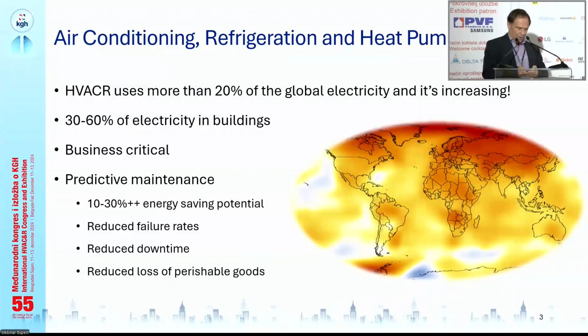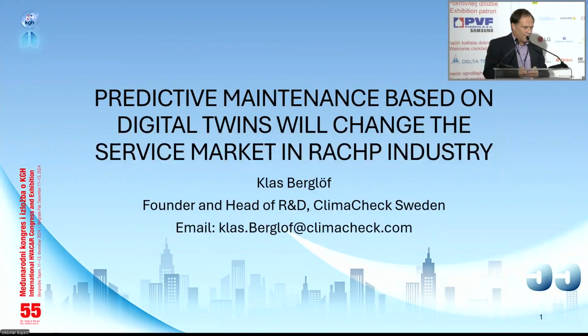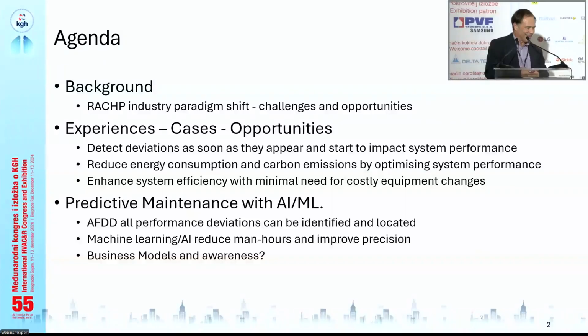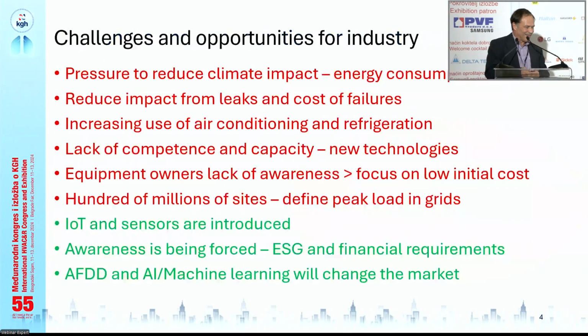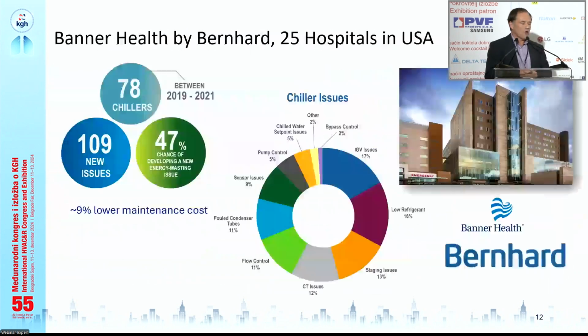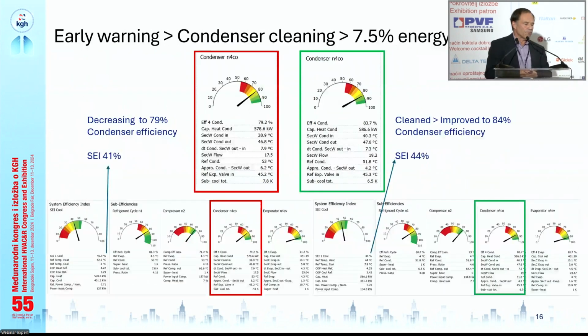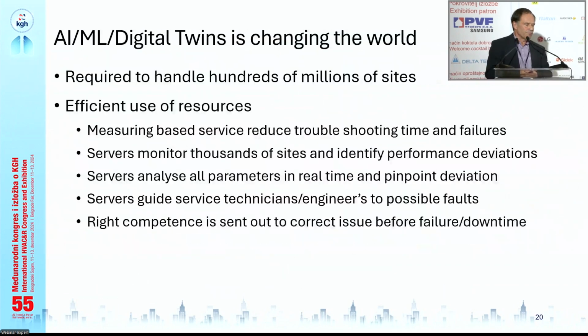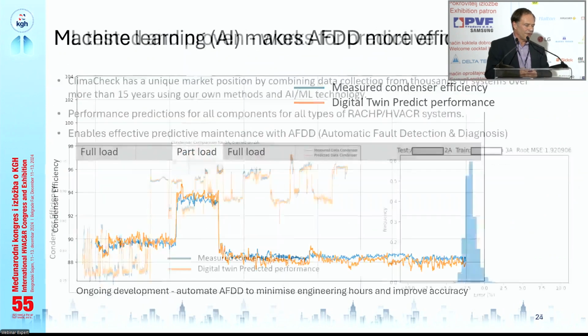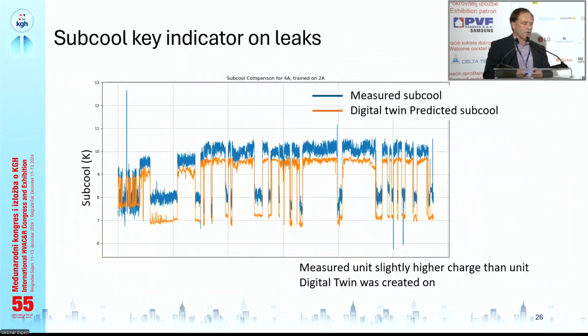Apologize for this. Yeah, so indirect leak detection is extremely efficient. You can detect leaks because they change the operational system, but subcool is a good indicator, but it varies naturally with operating condition. So if the digital twin tells you what it should be at these conditions, you can work much more efficiently.